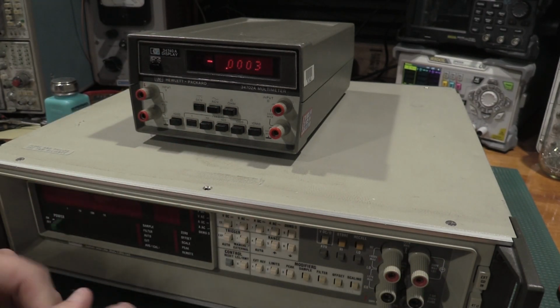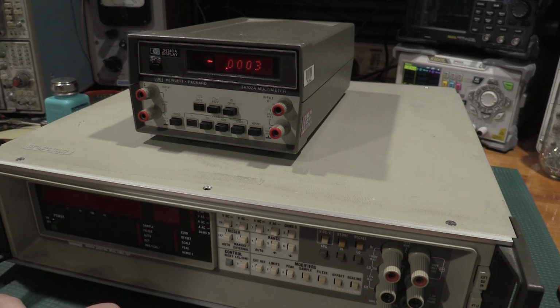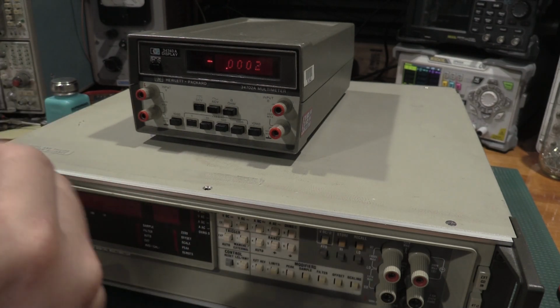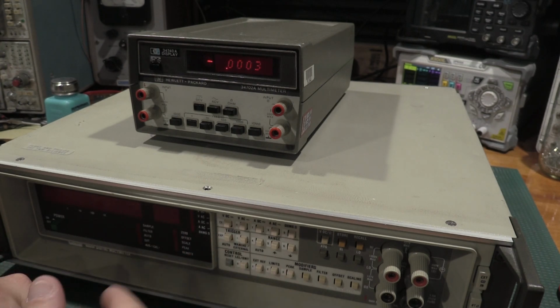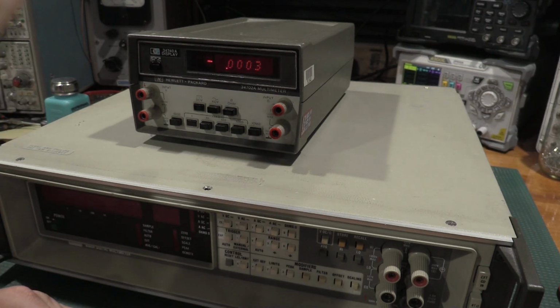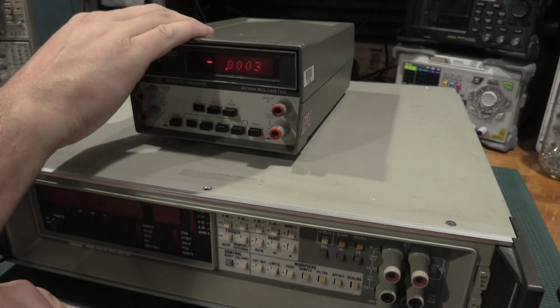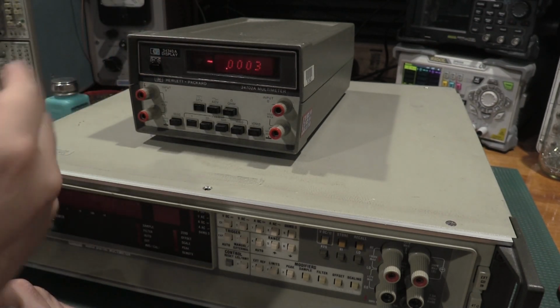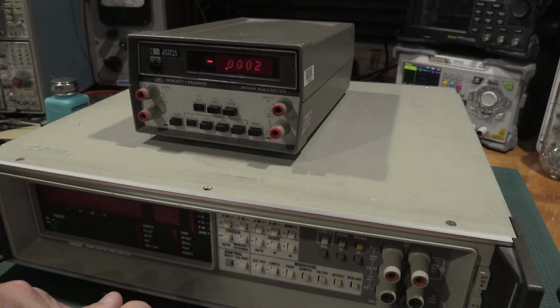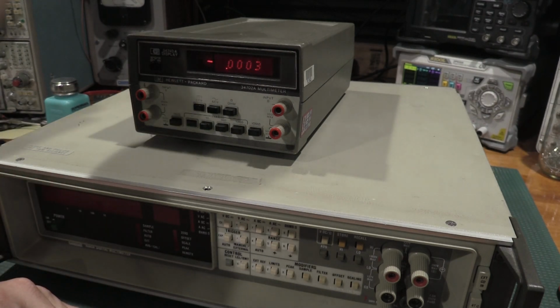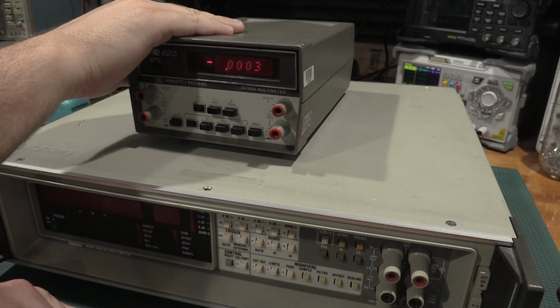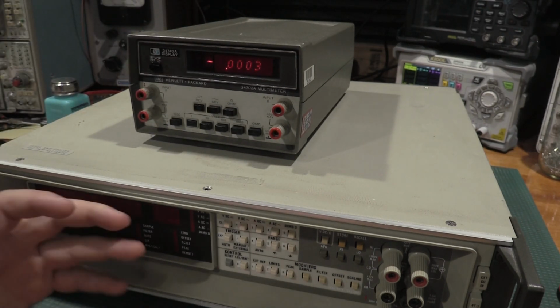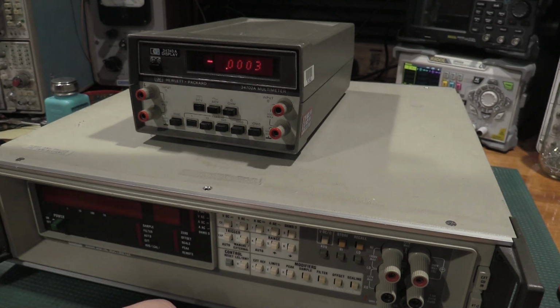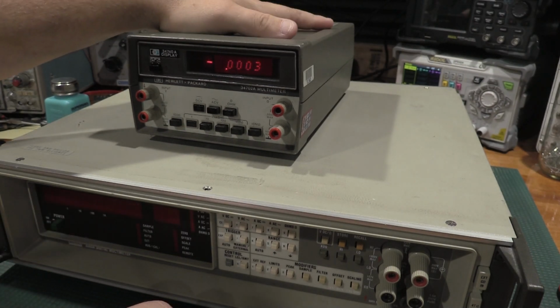Essentially what this was on a workbench where primarily the repair task that was done was going through UPS batteries, checking lead acid batteries, making sure they were okay, and doing some load testing and discharging and things like that. So complete overkill for that task. This will work just fine, nice small form factor, and it'll live again. So this is going back into production, not in this facility, but in a different one that is actually currently being renovated at the moment. So this is going to hang out here for a little bit, and then it's going to move on to its final resting place.